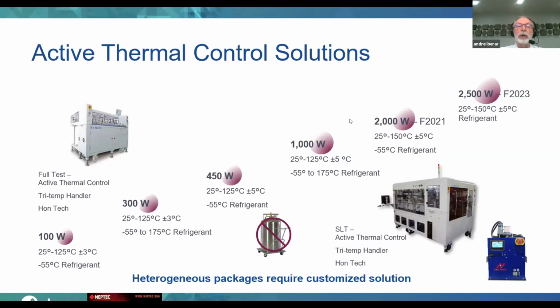Right now, there is well-known manufacturing proof of removing power through the thermal heads up to around 1,000 watts, moving towards 2,000 to 2,500 watt solutions. Again, the devices may not dissipate 1,000 watts, but we need to be prepared to take care of the spikes, which require overpowering - so we may need more capacity than the device itself dissipates under normal conditions.